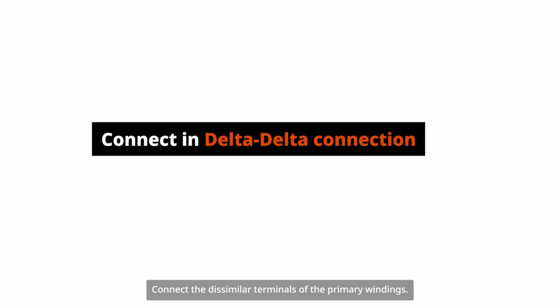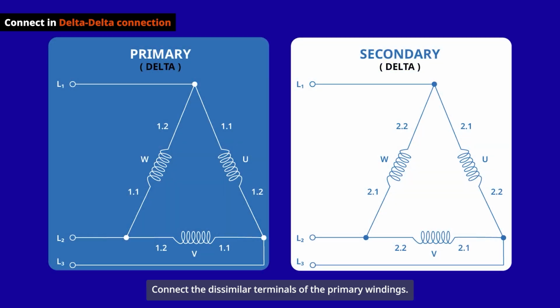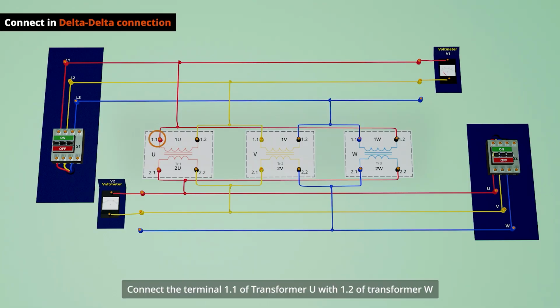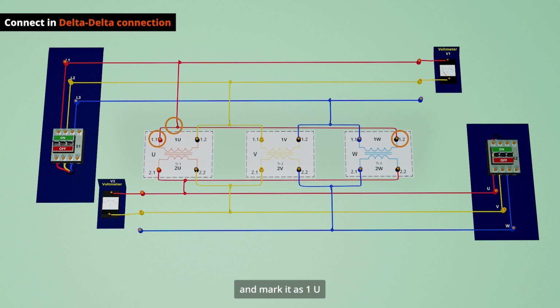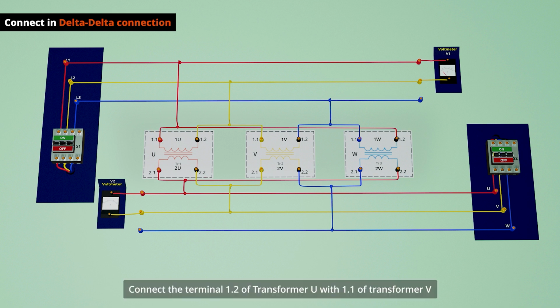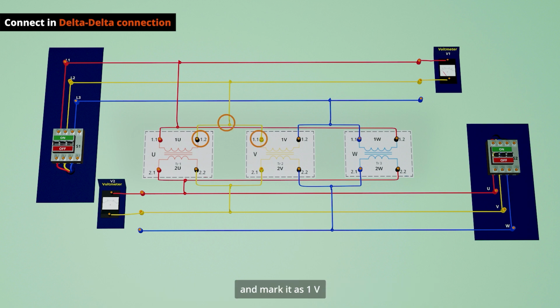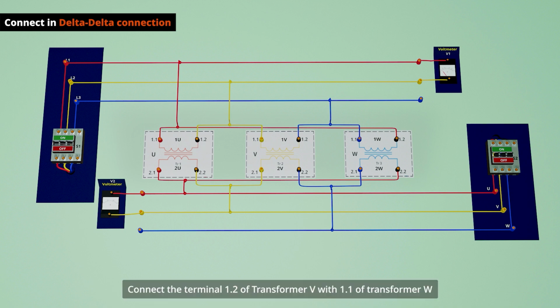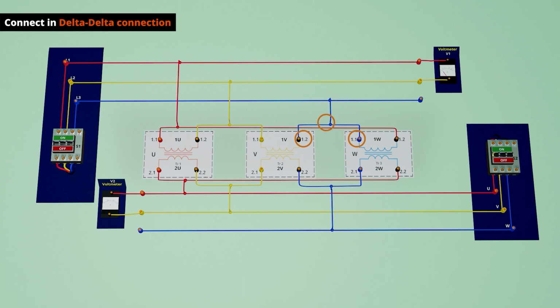To connect in delta-delta connection, connect the dissimilar terminals of the primary windings. Connect the terminal 1.1 of transformer U with 1.2 of transformer W and mark it as 1U. Connect the terminal 1.2 of transformer U with 1.1 of transformer V and mark it as 1V. Connect the terminal 1.2 of transformer V with 1.1 of transformer W and mark it as 1W.